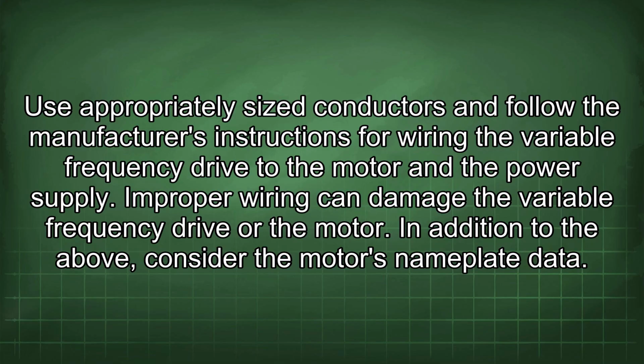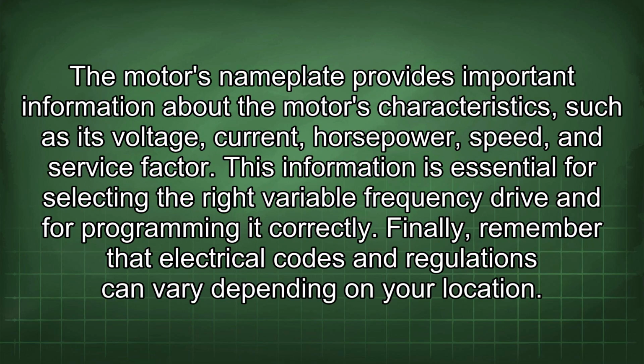In addition to the above, consider the motor's nameplate data. The motor's nameplate provides important information about the motor's characteristics, such as its voltage, current, horsepower, speed, and service factor. This information is essential for selecting the right variable frequency drive and for programming it correctly.